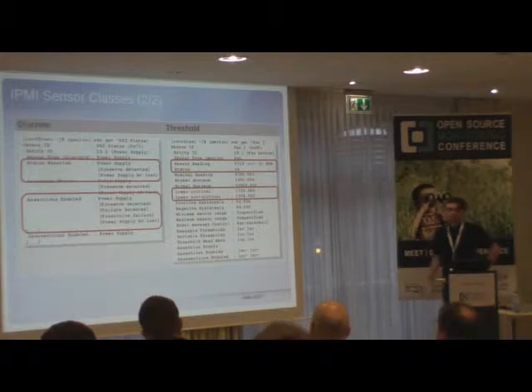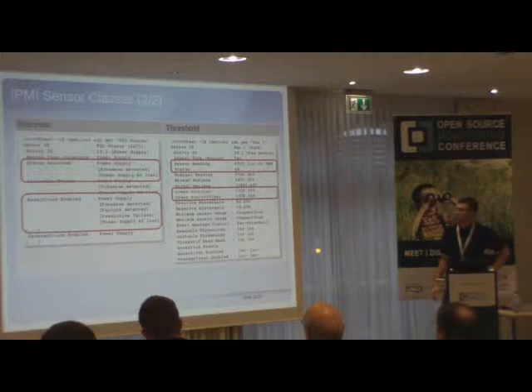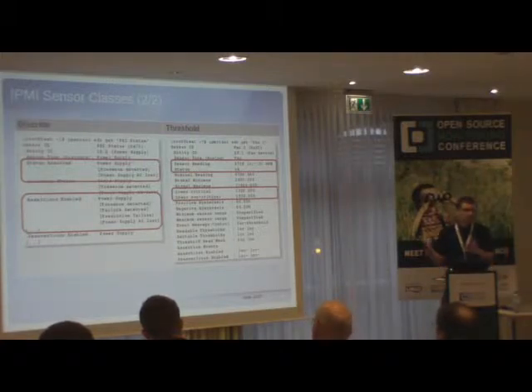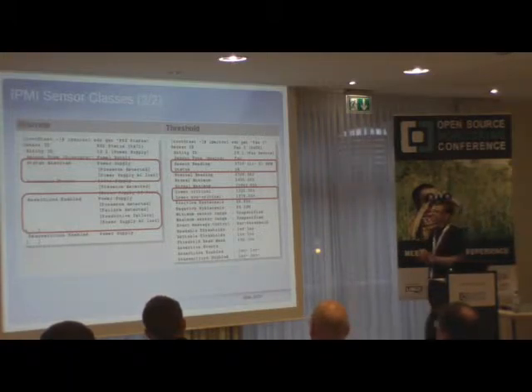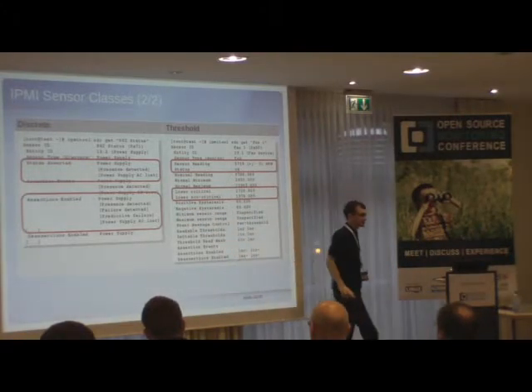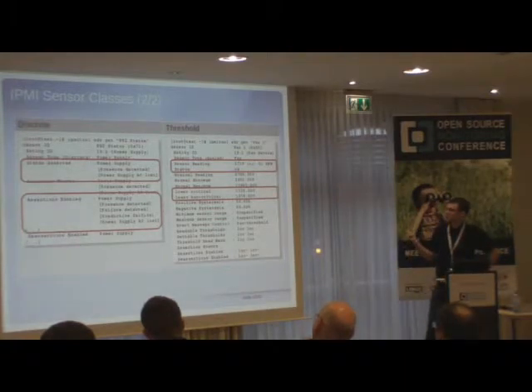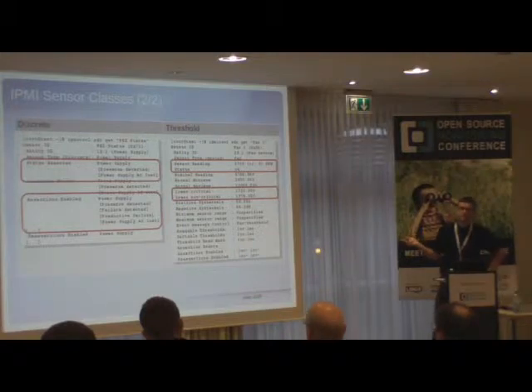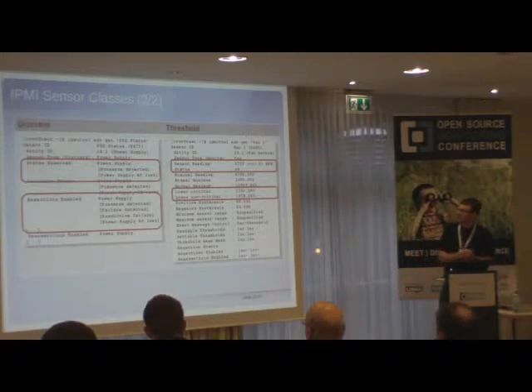We can see this on the example slides. On the left side we have a discrete sensor — a power supply from an Intel SR2500, a four or five year old system. This sensor can have four different states: presence detected, failure detected, predictive failure, or power supply AC lost. We see that the power supply has been detected and is present, but it has lost its power on the inlet.